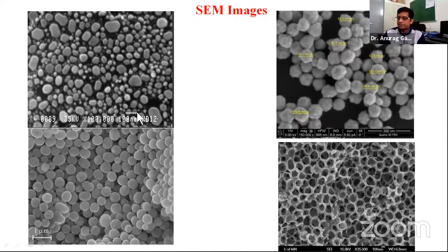Firstly, you measure this bar. Suppose this bar is 1 centimeter. So you could say that 1 centimeter is equivalent to the 100 nanometer. And suppose this particle size is 0.5 centimeter. So 100 nanometer is equivalent to 1 centimeter, then 0.5 centimeter will be equivalent to 50 nanometer. So by that way you can calculate the size of the particles. So size of the particles can be calculated with this approach.